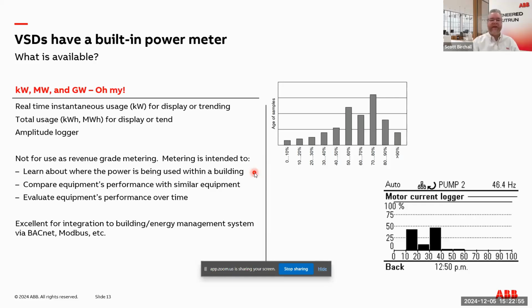You compare equipment with each other, and also just get a better idea where your power is being consumed in your building. Instead of just saying my mechanical room consumes this much power, now you can see my chiller consumes this much, my hot water pumps consume this much, my chilled water pumps, my condenser water pumps, my exhaust fans, my relief fans, my supply fans. You can really see that granularity. And with that data, you can start to make smart decisions and evaluate what you can do to reduce your energy bill.